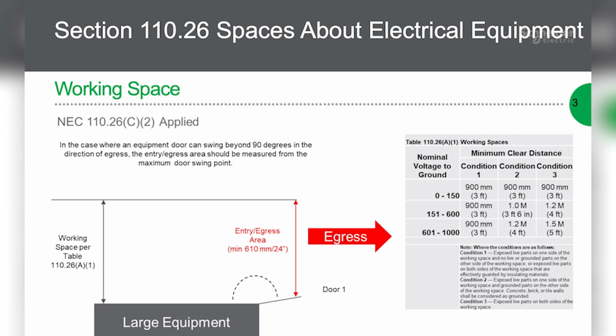So sometimes there's a little calculation you have to do to figure out how much the door protrudes into the working space. In this example, take a 480 volt switchboard with a grounded concrete wall at the edge of the working space. This would be a condition 2 for Table 110.26 and would require 3.5 feet, or 42 inches, of working space clearance. If we take a standard switchboard door that's 30 inches wide and opens 120 degrees, we calculate that we're protruding into the working space 26 inches. With 16 inches remaining, we no longer have that 24-inch egress path you just mentioned, Toby. So the electrical room has to get bigger to accommodate that. I think that's a big issue to consider.